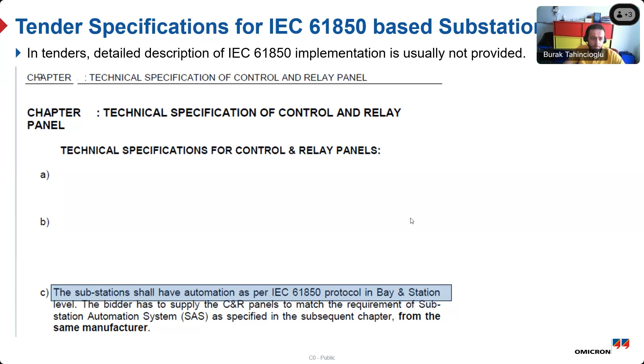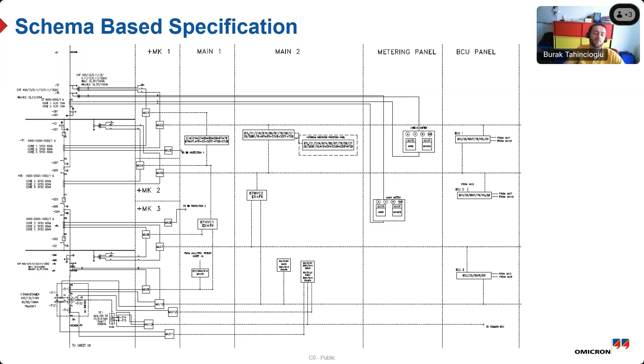Often there was the schema-based specification, even still with 61850 substations, where we define maybe the ANSI codes and the protection, control, measurement functions over the single line diagram with the primary equipment, and allocate the IEDs as boxes which have tasks or functions to be taken from the single line diagram. We show the primary equipment and then the allocations for the IEDs into this primary equipment, which are the functions abbreviated with the ANSI codes. That was the traditional way until now.